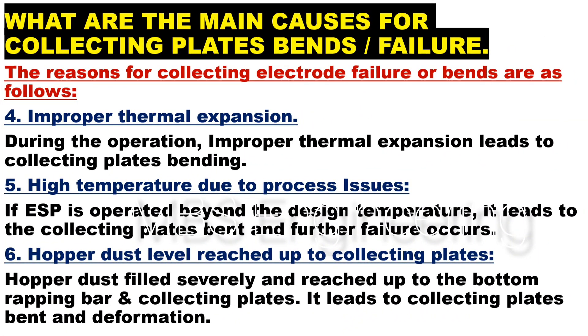One of the causes for collecting plate bends is improper thermal expansion. During the operation, improper thermal expansion leads to collecting plates bending. High temperature due to process issues: if ESP is operated beyond the design temperature, it leads to the collecting plates bending and further failure occurs.